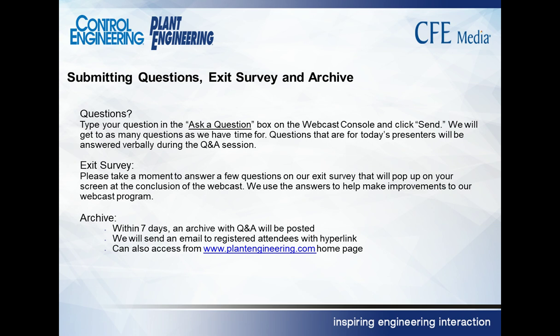We had another question up there that went away. There it is. The question, as you mentioned, BEP is 85%. What do you mean? Is 85% of closed head or what? If you looked at the formula that said flow times head divided by some constant, in our case 3960, equals brake horsepower. If you just ignored the efficiency part, you'd have the gross amount of horsepower that was needed. Let's say I do that, my head times my flow, and I'm not going to throw numbers out, but let's say the total comes out to be 100 horsepower. I need 100 horsepower to run this pump to get that amount of flow and head.